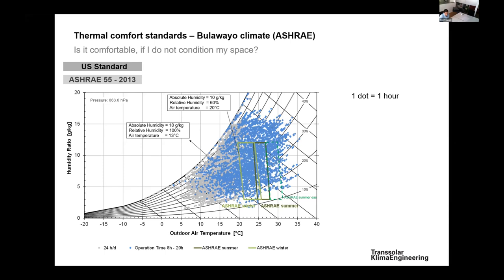According to ASHRAE, in Bulawayo you have to do something. At some parts of the year — winter — you need to heat. At summer peaks, you need to cool or increase air movement to achieve comfort. Sometimes you are also too humid, above 12 grams of water per kilogram of air, so you need to dehumidify. The conclusion: if you do not condition your space, you are not comfortable according to the ASHRAE standard. It doesn't mean it's always terrible, but the standard is not achieved.